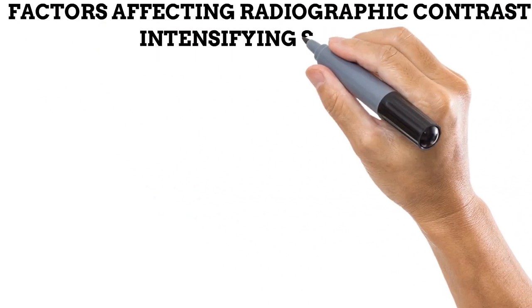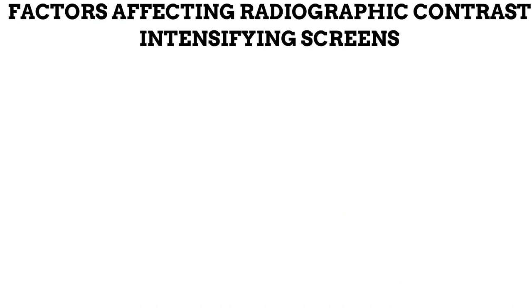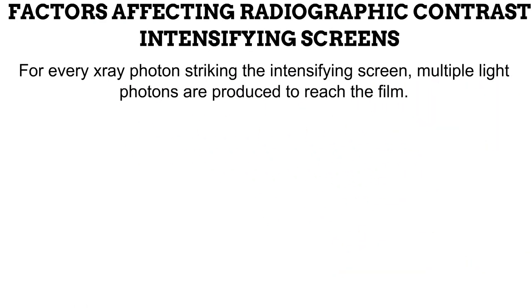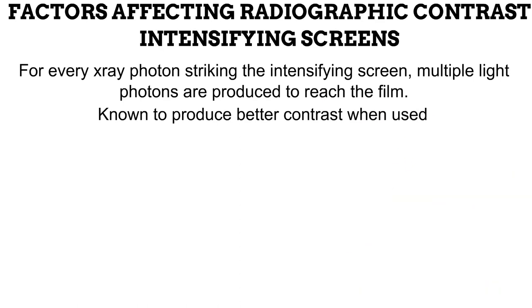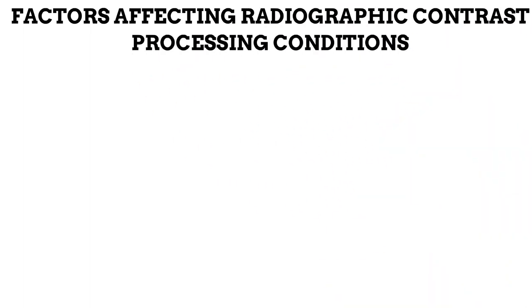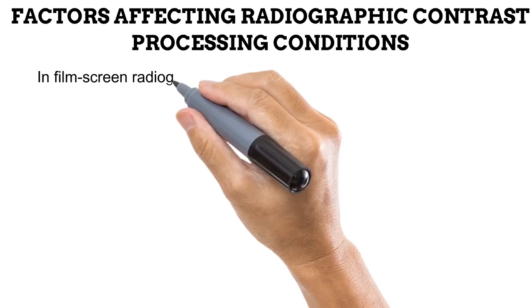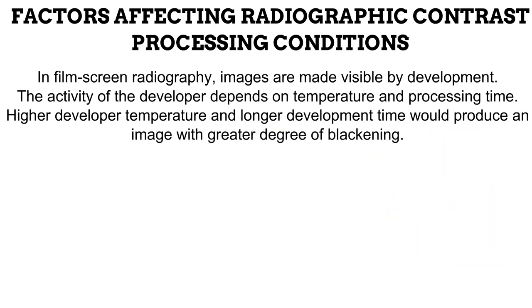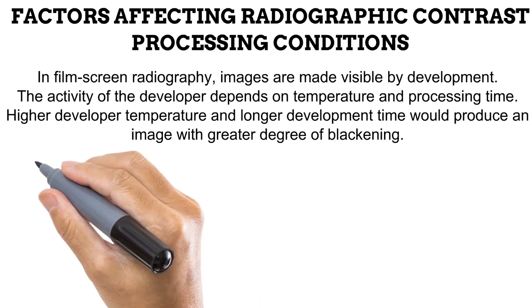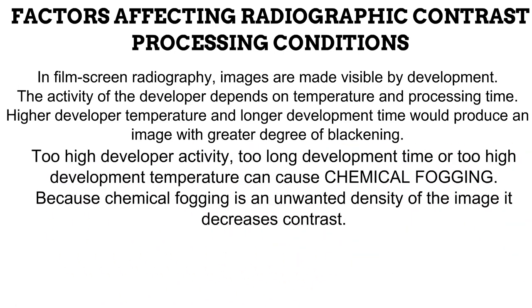The next factor is the use of intensifying screens, which applies only to film screen radiography. When intensifying screens are used, a multiplier effect on photon production occurs, and they have also been observed to produce greater contrast compared to when they are not used. Also applying only to film screen radiography are processing conditions. Images are made visible through a process called development, and the activity of the developer chemical depends on temperature and development time. At high temperatures and long development times, great density is recorded. However, if developer activity is too high due to excessive temperature or time, chemical fogging occurs — the formation of useless densities on the image — which decreases radiographic contrast, just as scattered radiation does.